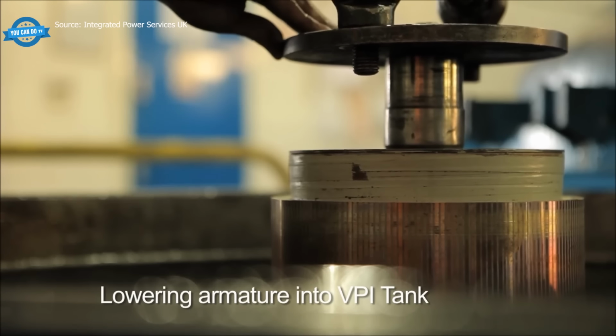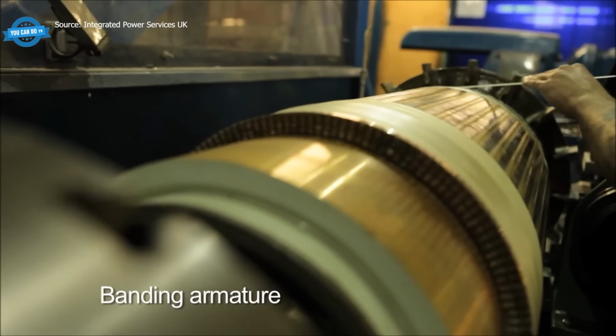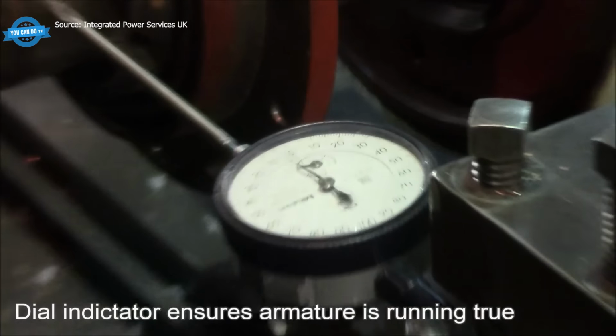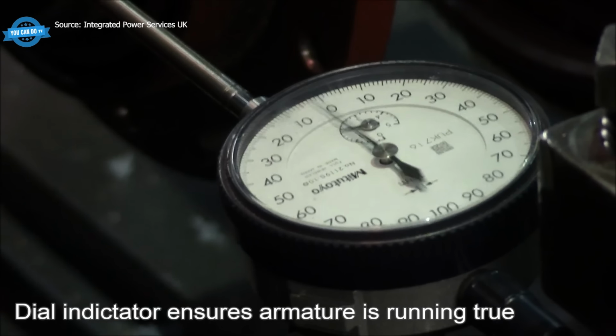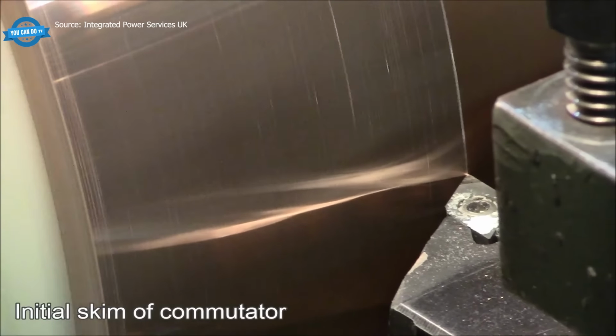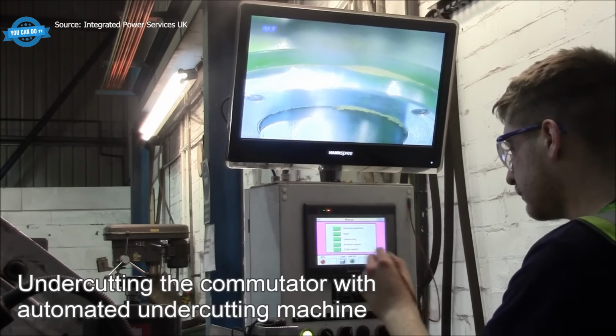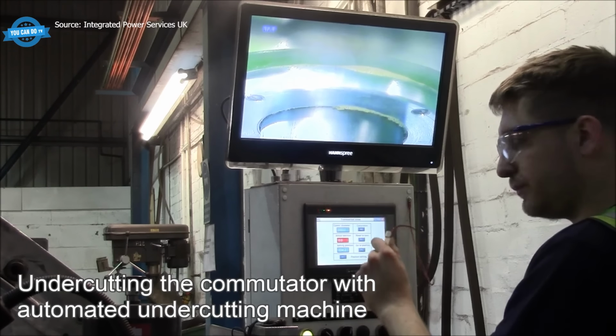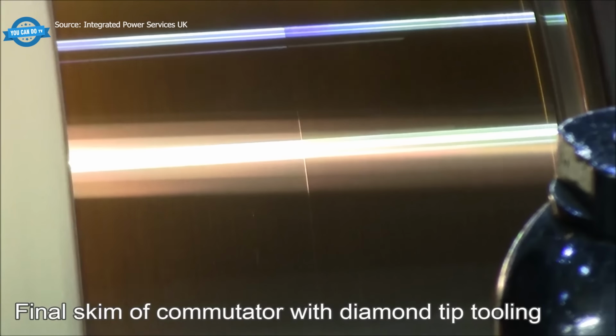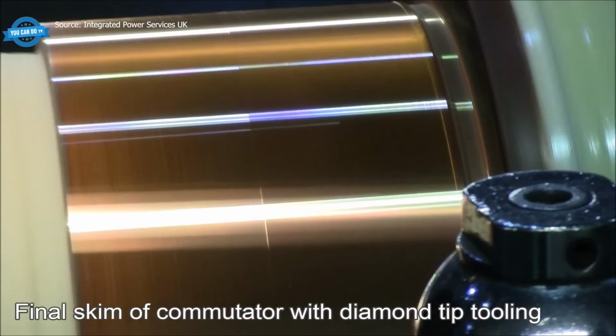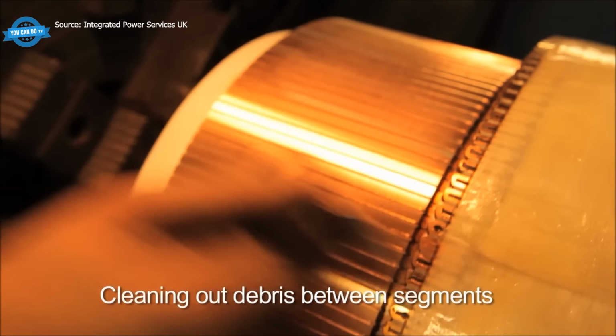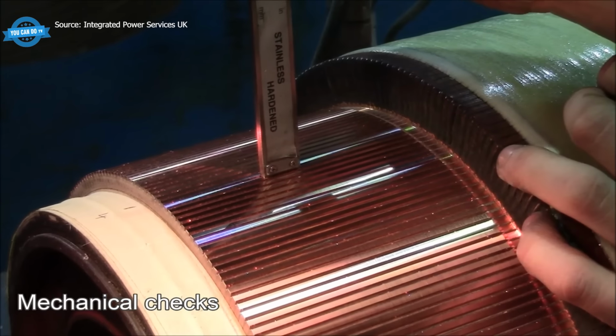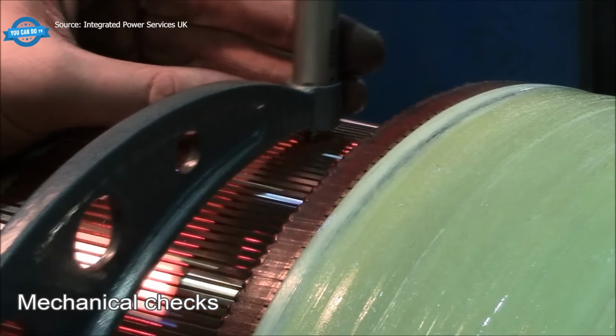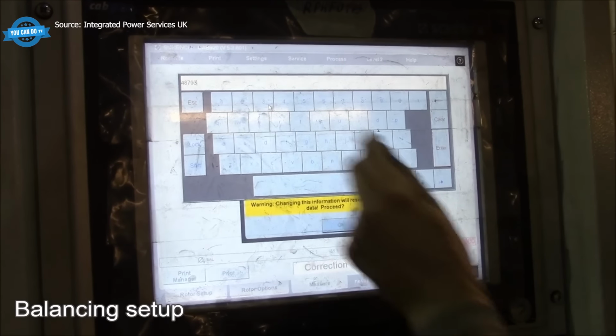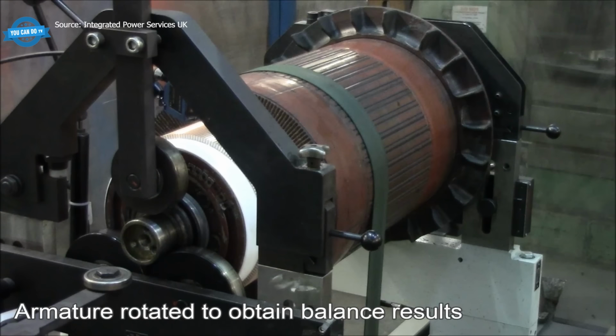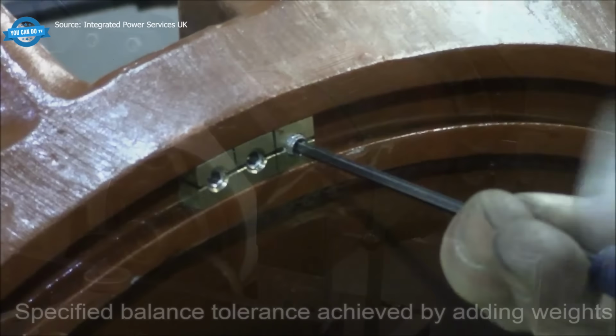The armature enters a vacuum pressure impregnation cycle where resin is forced into all internal voids under controlled pressure and then cured. Once hardened, the winding is banded for centrifugal strength. A dial indicator checks runout before the commutator is skimmed on a lathe. Laser-guided undercutting machines the insulation between segments to exact depth, followed by diamond tool finishing for brush contact surfaces. Finally, dynamic balancing is performed, with correction weights added until specification is met. A complete inspection report is printed before release.